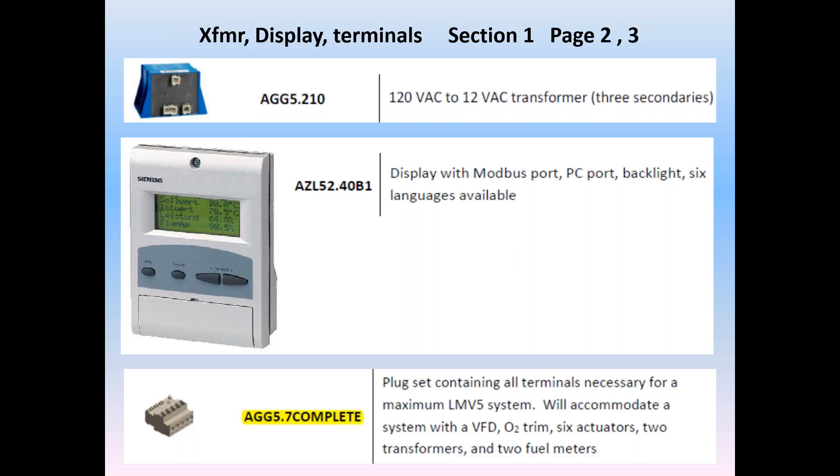It offers seven international languages, a four-line backlit display, a PC port interface for backup and optional programming, and while it can be programmed with a PC, typical commissioning on the LMV5 is done solely with the AZL. And finally, along with the burner and operating system CAN bus components, it also has a standard equipment, a Modbus port for BMS integration. All parts of the LMV5 system are sold individually, and terminal set options are shown throughout section one of this technical instructions.